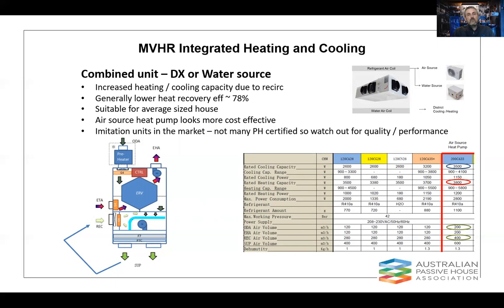It is potentially what you see highlighted in PHPP as your heating cooling load, but noting if we just match that, we're really going to get something that's great in steady state operation. But what we've found through experience is the recovery if you let the indoor temps run away. The classic example has been someone goes away, doesn't close any blinds, doesn't do any purge cooling at night, and the building overheats a bit. They come home, put their integrated cooling on, and it takes a long time to get that temperature down. And that could be many hours. It could be 6, 8, 10, 12 hours, which for a reasonable proportion of people is unacceptably long. So the aim has always been to try and boost that heating cooling capacity.